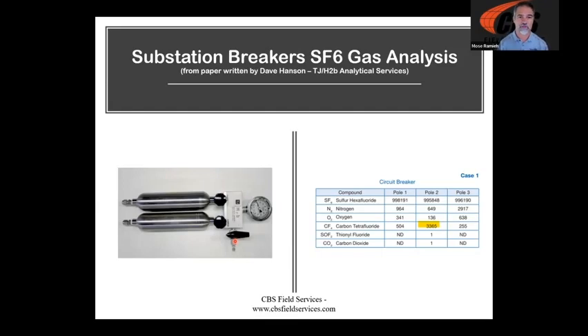So how can we get that same information by being less intrusive? And one way to do it is by taking an SF6 gas sample, not just for moisture or SF6 density, but to get into the decomposition products, because there are some really smart chemists out there that can tell you that if you've got a sulfur hexafluoride environment and you create an arc with various components that make up our breakers, like tungsten and Teflon and stuff that I probably couldn't even pronounce, you'll get byproducts, right? And these byproducts can be an indication of problems.